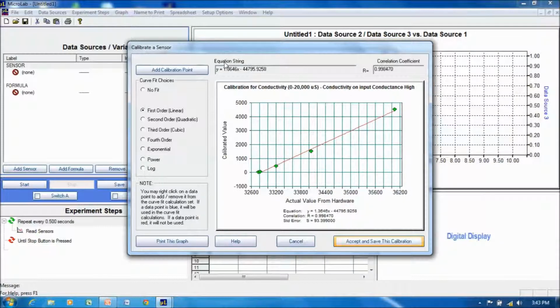So the cell constant for this particular Microlab Model 160 sensor that I'm using is on the order of 1.36 per centimeter. Okay? Now again, if you wanted to get a better value, you would do the calibration over a much smaller range, no more than 2 orders of magnitude. But we have enough data points, why not? Let's just add a second order fit to it. We lose specific information about the nature of the cell constant, but we do have a good relationship between the microsiemens per centimeter and the measured value from the hardware, and we have an excellent correlation coefficient that way.